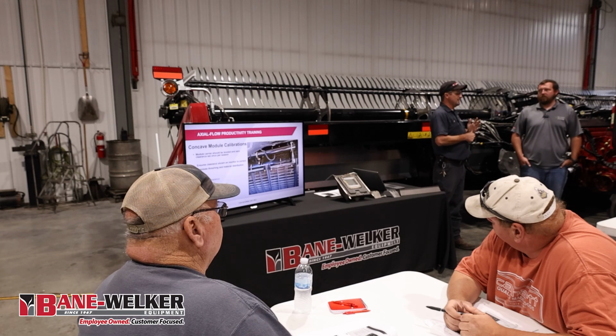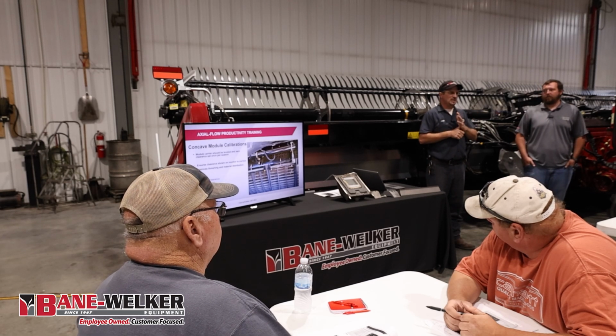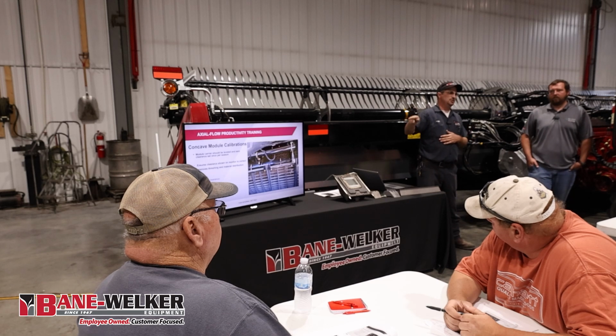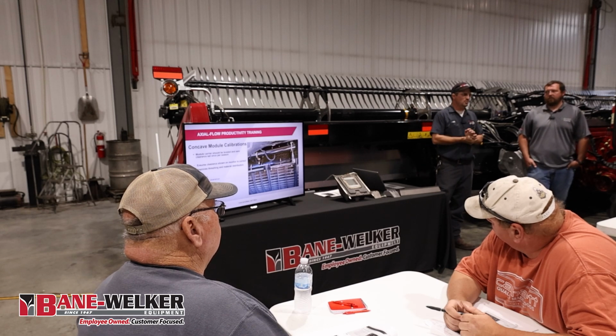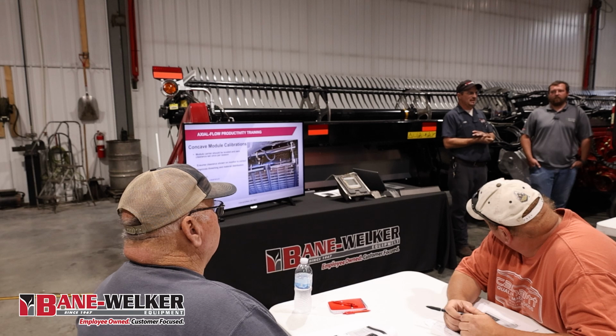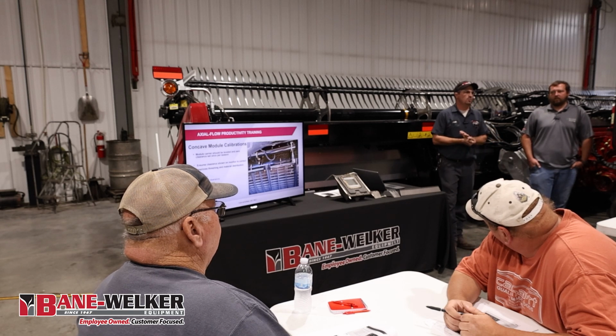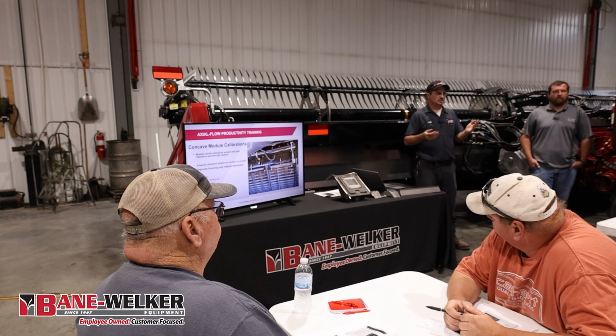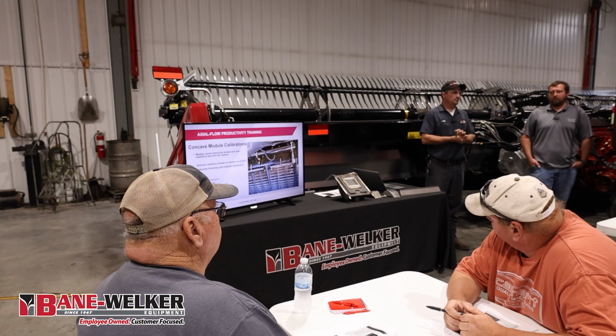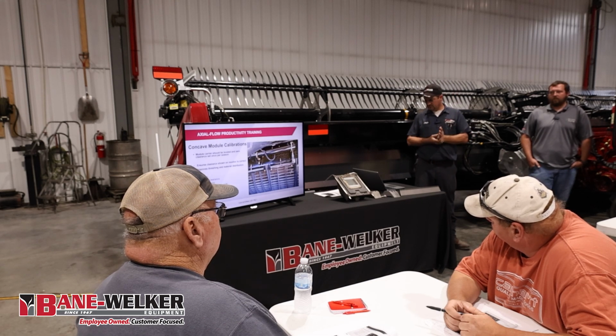The one thing I have seen is there is potential for a slight difference in wear on your modules too. They do wear as well. So if you throw a different module in there, you may want to reconfirm that set point, okay? It takes just a matter of seconds to turn that over and confirm that you have clearance, okay?